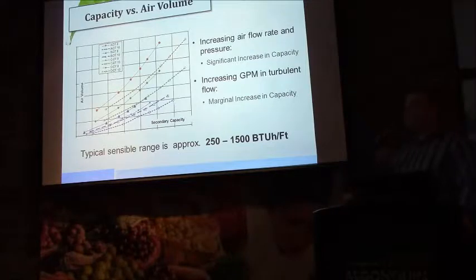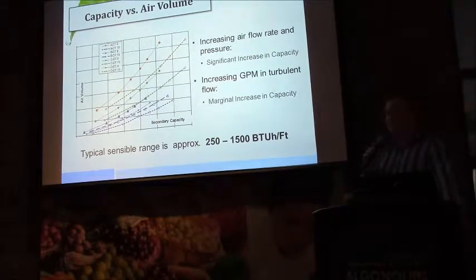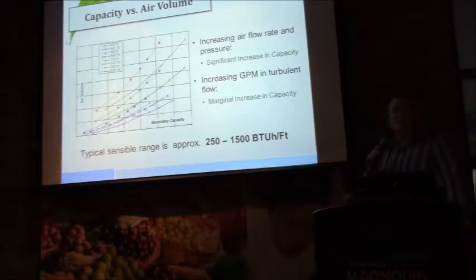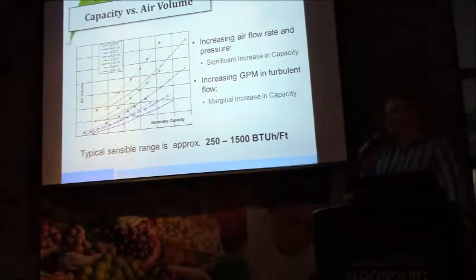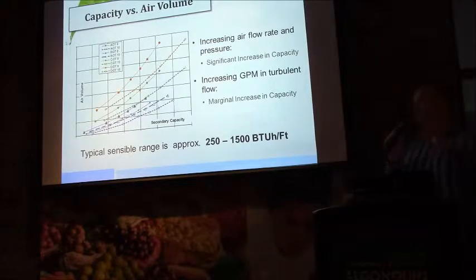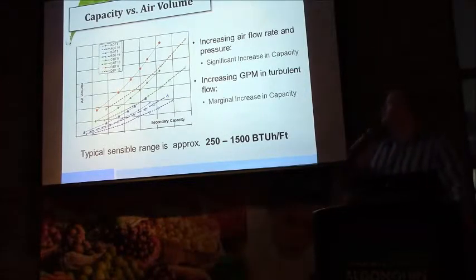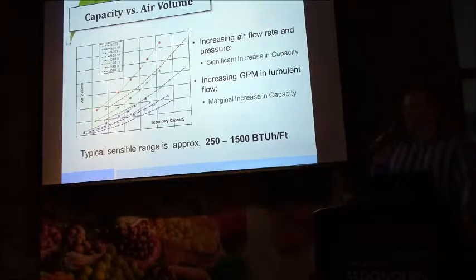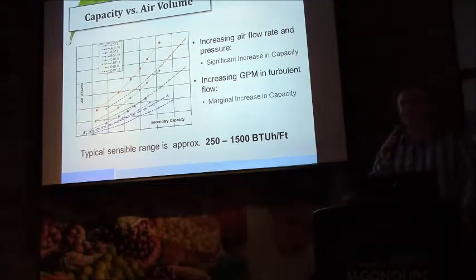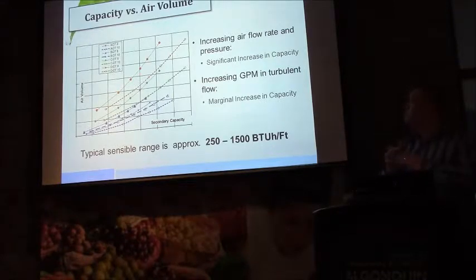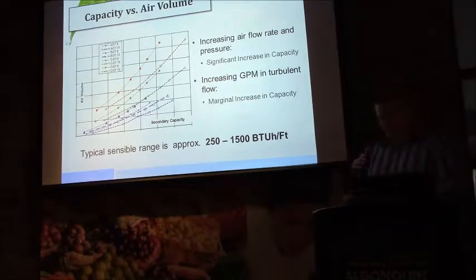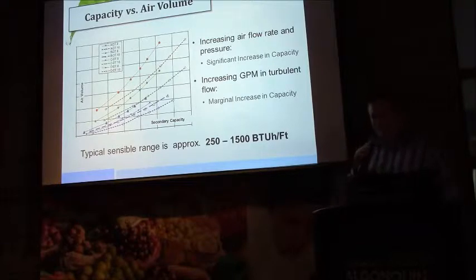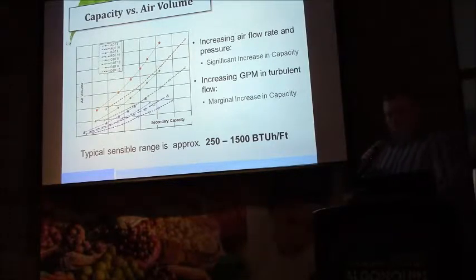The net benefit of the selection process is such that increasing the air side consumption yields greater overall capacity than increasing the flow rate. So doubling the water flow rate in the beam may yield 10 to 15% more capacity, where earlier we discovered that doubling the pressure, not necessarily the volume, but doubling the pressure in the beam could conceivably increase the capacity by 70%. And these are typical capacities capable of being 250 to 1500 BTUs per linear foot.